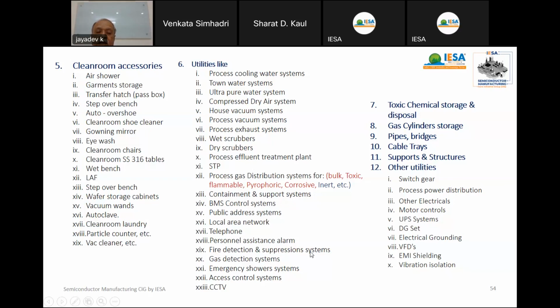Therefore, semiconductor fabs normally recommend the FM200 gas suppression system rather than going for water spray. Because if you use water spray, a lot of costly equipment may get damaged, and also a lot of process wafers may get damaged. So go for a gas suppression system, gas detection system, then emergency showers, access control, etc.